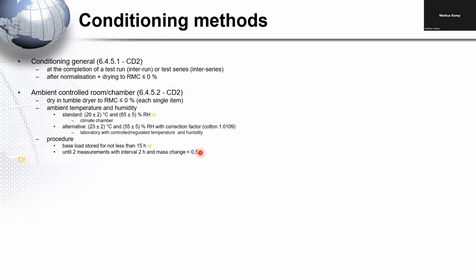But what is important, if you use a climate chamber or the laboratory room, is that you log all the data at regular intervals so that you are sure that within this 15 hours or 2 hours, whatever you use, the climate has not exceeded the given tolerances. So therefore, you have to apply a data logger system or something like that, which is measuring the ambient temperature and humidity in the chamber.